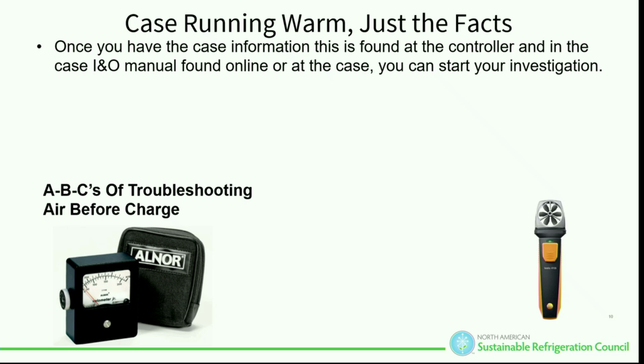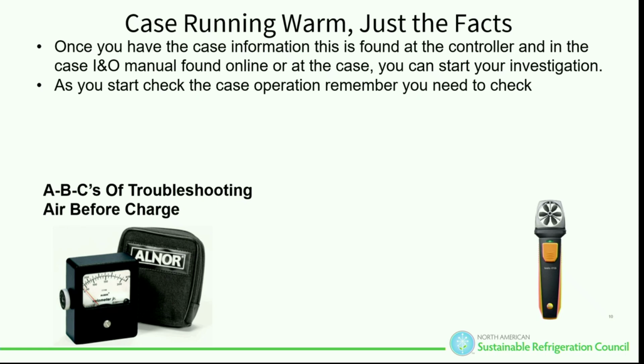Typically with air conditioning, we do CFM. In this instance, we typically do FPM, feet per minute. If that feet per minute is not right, it will affect everything else down the line as far as your diagnostic properties. And good isn't a form of measurement. I don't know how many times guys have called me and it's like, yeah, the airflow's good. What's good? As you start to check the case operation, remember what you need to check. Airflow, first.